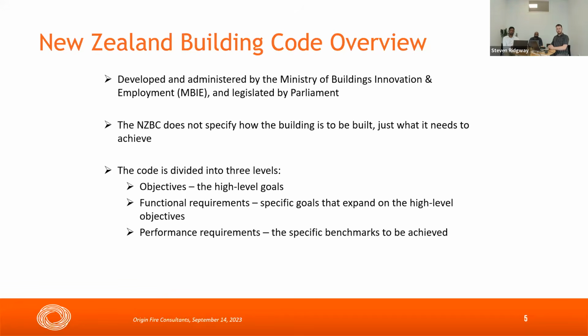And then past that, you get the performance requirements, which are very testable and quantifiable, and they're a specific benchmark. Examples, I'm not going to read it out to you. Clause C4.3 is quite a long one, but it tells you that occupants must be able to evacuate safely without being exposed to untenable conditions, such as toxic gases, loss of visibility, or excessive heat. There are benchmarks, but your fire engineer will tell you when you do your project.